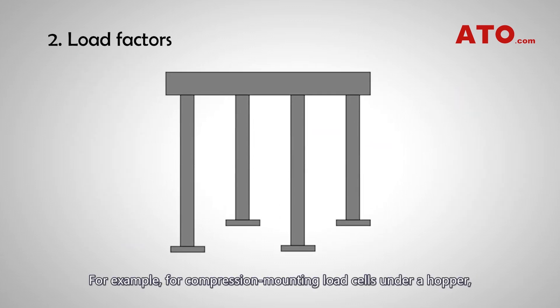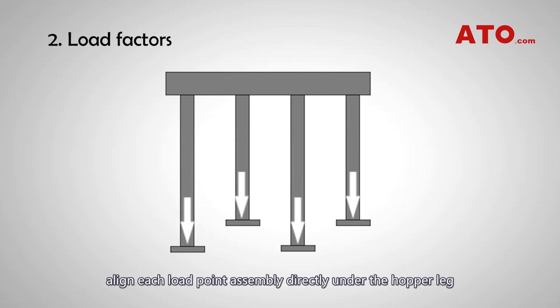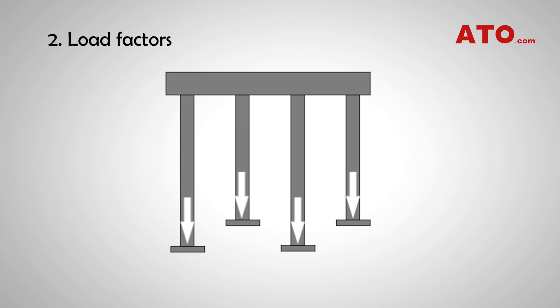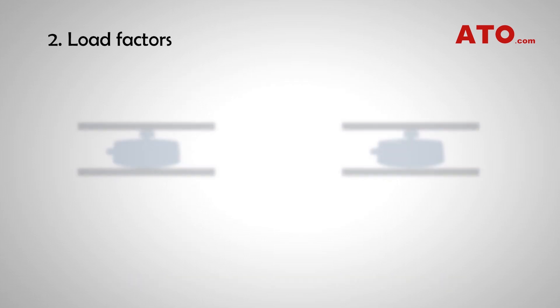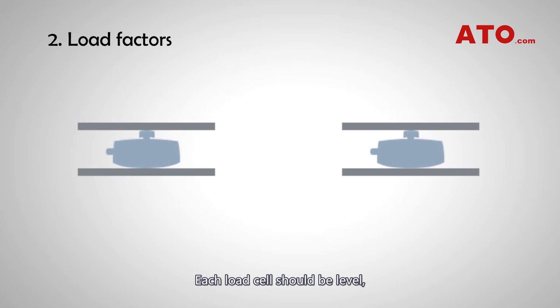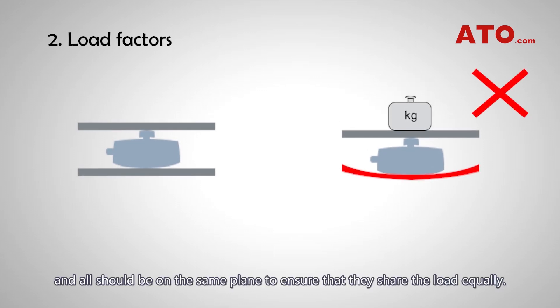For example, for a compression mounting with load cells under a hopper, align each load point assembly directly under the hopper leg to avoid pulling or pushing between assemblies on the other legs. Each load cell should be level, and all should be on the same plane to ensure that they share the load equally.